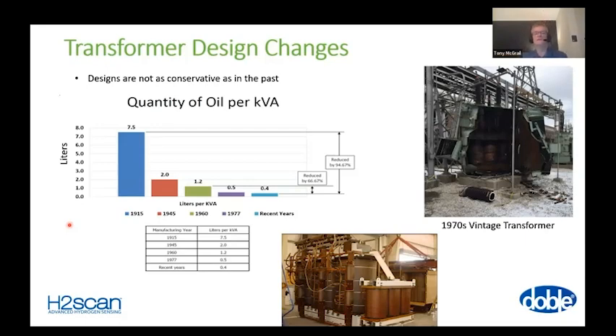The transformer at the bottom in the middle, that's the guts of a transformer after it had been taken away from site after it had failed. It was very difficult to inspect internally, but you can see the 3 main windings off to the left, and on the right we've got what's called the preventative auto, which helps regulate the voltage on the tap changer. And within that preventative auto, a brazed joint had come apart, and that had led to huge amounts of heat generated at the poor joint. And we had temperatures on the tank next to that in excess of 200 degrees C. That was a transformer we tested ad nauseam, to quote Leon from earlier, and we got lots of information, said we can't fix it on site, take it back. They fixed it, put it back in service, and away they went.